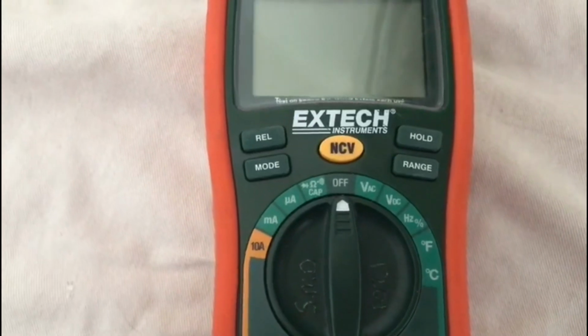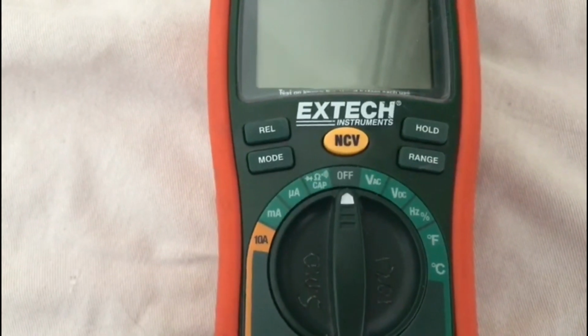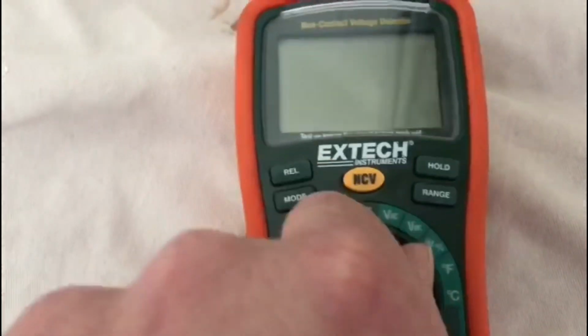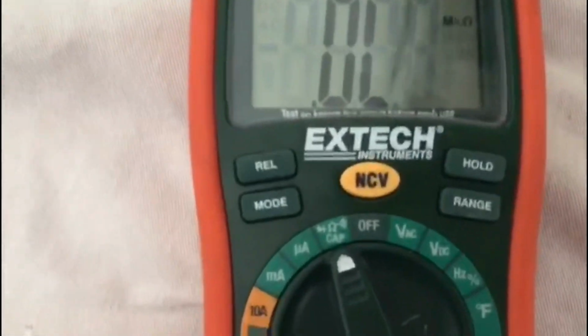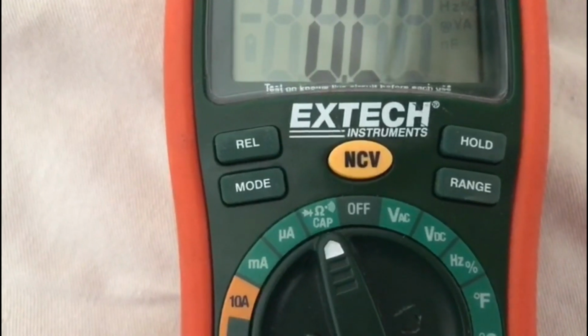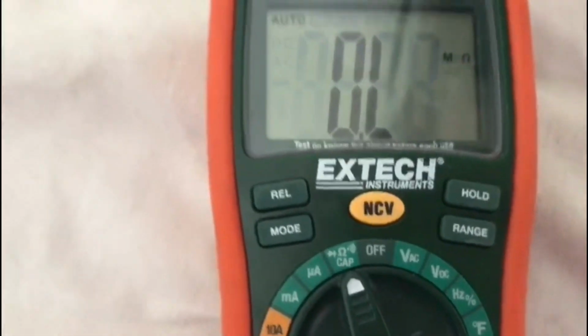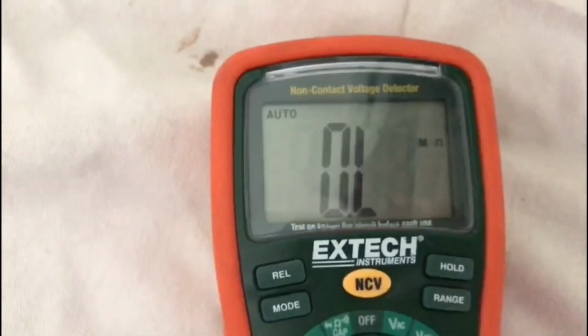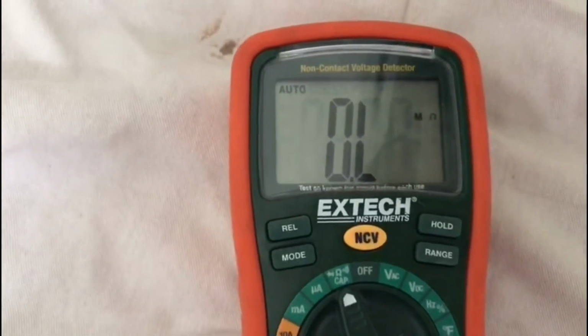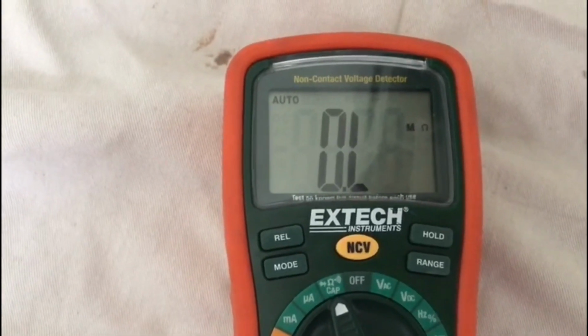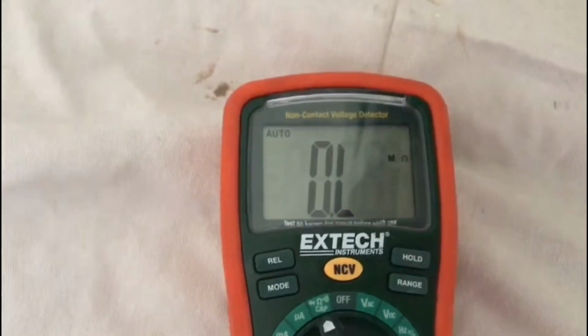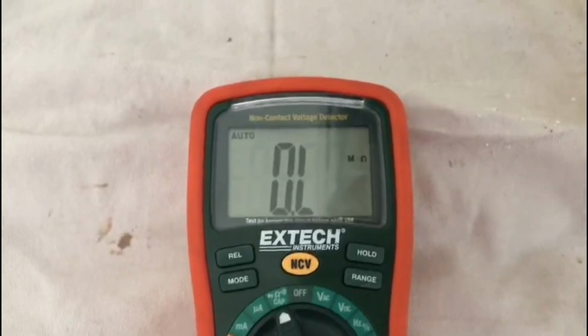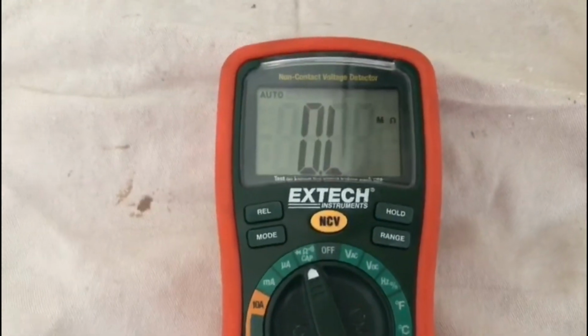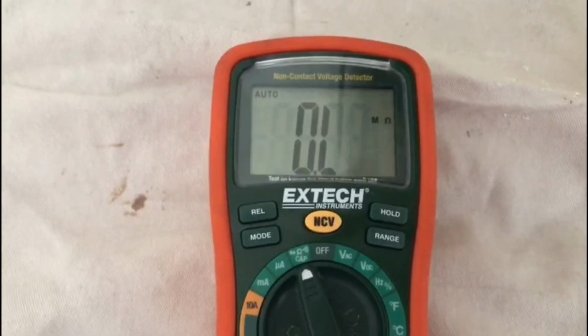But this multimeter which I've got is a pretty basic one. For your short circuit test, resistance to earth, and earth continuity test, it needs to be set to continuity or ohms or resistance, whatever you want to call it. But you should have an open line. When your 2 probes are separated, you have open line or infinity. That means that they're not in contact and that the actual reading is infinity. There's no way that they can touch unless you bring them together. So that's the reading you want to start off with first.